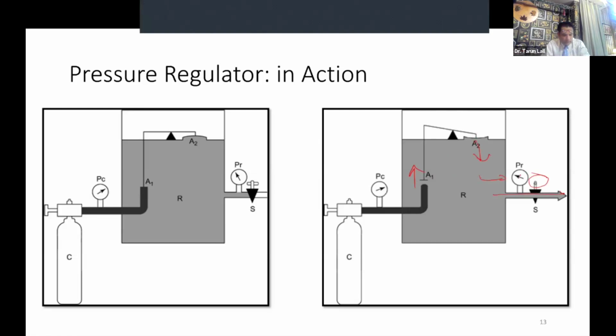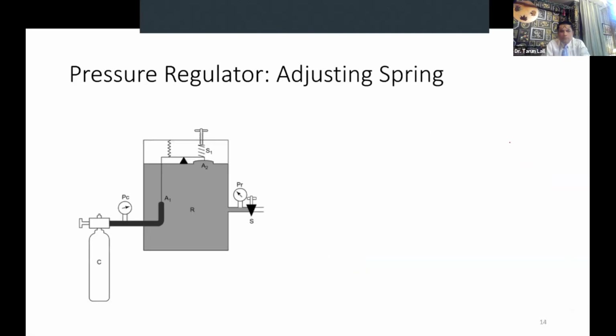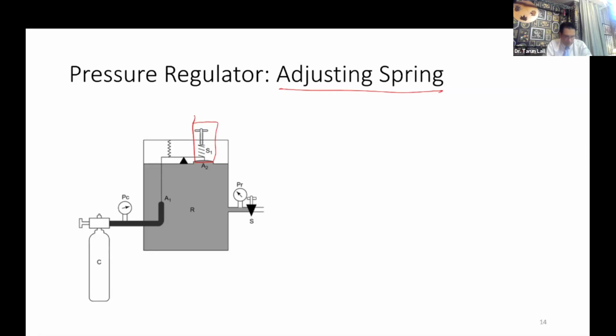But the problem is that as the cylinder pressure keeps on falling, the output pressure will also keep on falling, and therefore I will have to be vigilant. I will have to keep on adjusting the flows to match the cylinder output. So what did the engineers come up with? They came out with the idea of an adjusting spring. In this design, what has been added is this spring S1, which is a very large force as compared to the other forces we were talking about, so that changes in the other pressures become inconsequential.